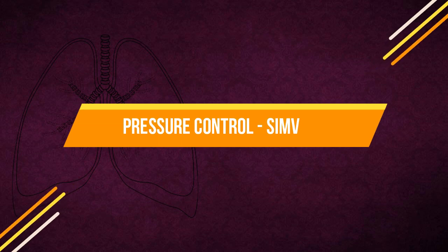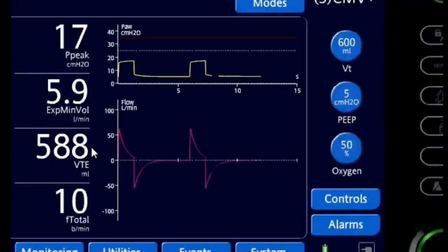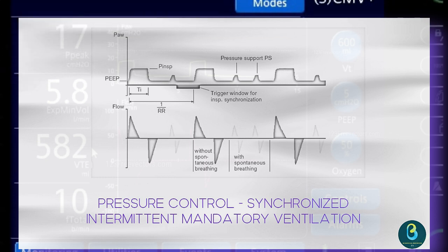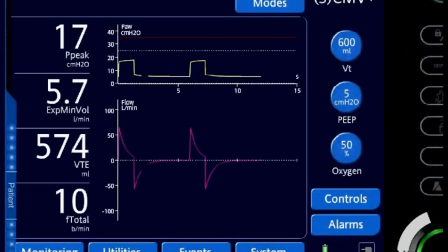The next mode in Pressure Control is Pressure Control Synchronized Intermittent Mandatory Ventilation. The patient can breathe spontaneously at any time, but the number of mandatory breaths is specified. The mandatory breaths are synchronized with the patient's own breathing attempts, and a patient-triggered mandatory breath can only be triggered within a trigger window. If the expiration phase and spontaneous breathing time is shortened due to synchronization, the next expiration phase will be extended, preventing a change in the number of mandatory breaths.